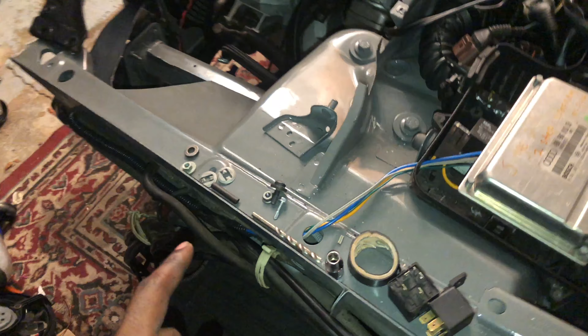The reason my fan stays on is because of the probe wire - it says 22 gauge right there. I was supposed to use 2 separate 22 gauge wires and extend it all the way to my probe. So if you want to extend your probe wire, make sure when you slice it in half to use 2 separate 22 gauge wires to extend it. That's the reason my fan is staying on - the probe actually shorted out. I basically shorted out the probe.